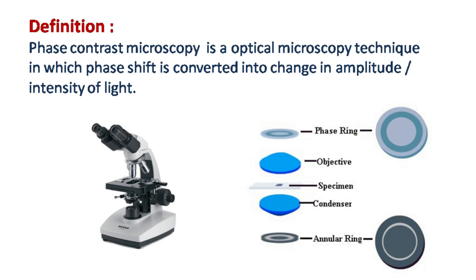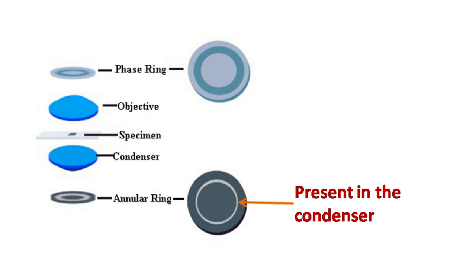Let's see how phase contrast microscope works. The phase contrast microscope has two components: annular diaphragm and the phase shifting ring. The annular diaphragm is a ring-like slit present in the condenser, while the phase shift ring is present in the objective.